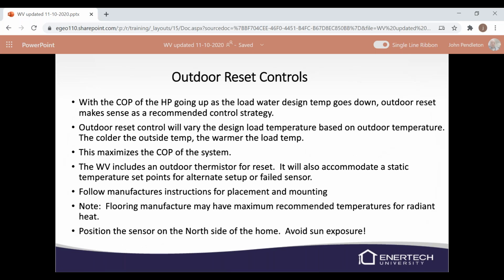Outdoor reset, we talked about that a little bit, with your outdoor air temperature sensor that comes with the unit. Basically, we'll use that outdoor temperature for our outdoor reset control. So with the efficiency of the unit, or the COP of the heat pump, going up as the load design temperature goes down, then outdoor reset makes a lot more sense as a control strategy. It's basically going to vary your design load based on your outdoor temperature. So the colder the outdoor temperature, the warmer the water will be. When it's 50 degrees outside, we don't need 120 degree water running through your floor to get temperature. So we can lower that water temperature and improve our efficiency of the unit.